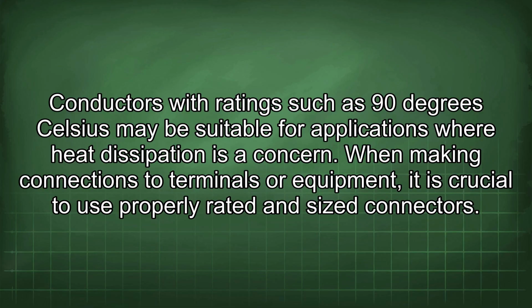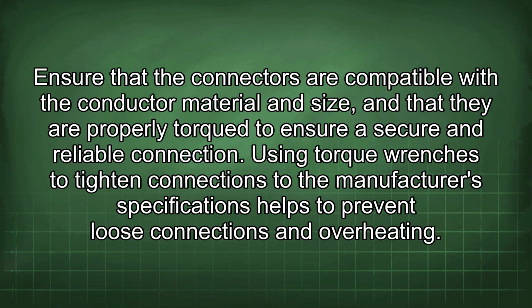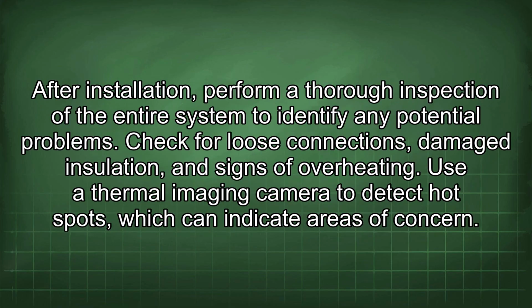When making connections to terminals or equipment, it is crucial to use properly rated and sized connectors. Ensure that the connectors are compatible with the conductor material and size, and that they are properly torqued to ensure a secure and reliable connection. Using torque wrenches to tighten connections to the manufacturer's specifications helps to prevent loose connections and overheating. After installation, perform a thorough inspection of the entire system to identify any potential problems.